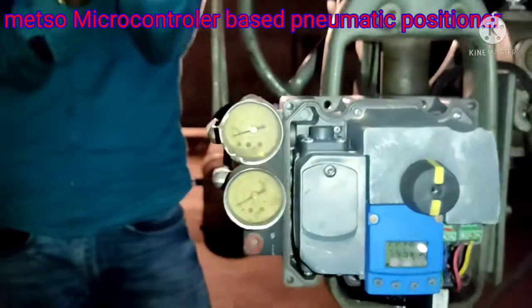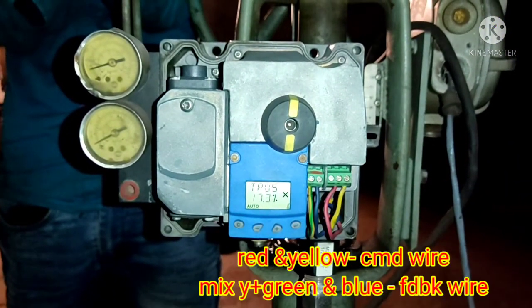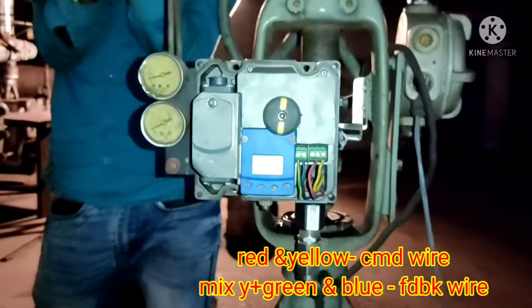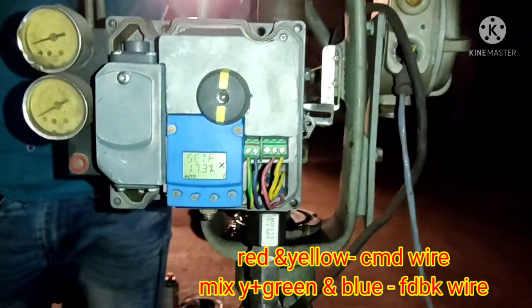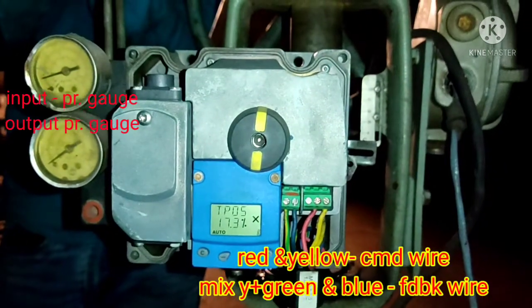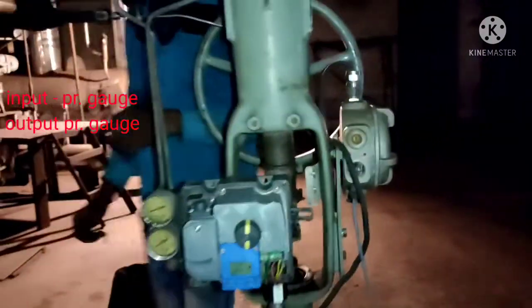After removing the cover of the positioner, we see the display part — this is called LUI, which stands for Local User Interface. On the right side you can see the red and yellow wires: the command wire and the 4-20mA loop wire, along with yellow, green, and blue feedback wires. Through these feedback wires, the position signal goes to the DCS system. The positioner has two gauges: one input pressure gauge and one output pressure gauge.